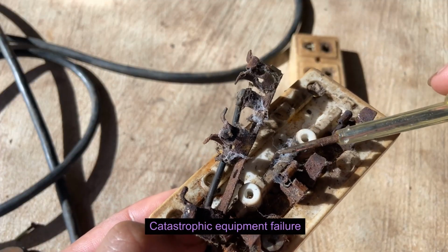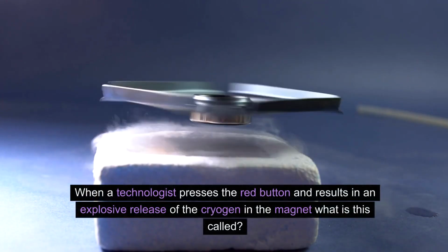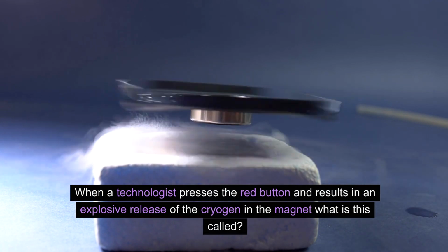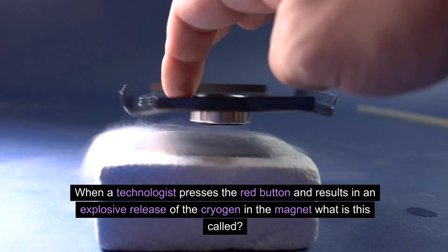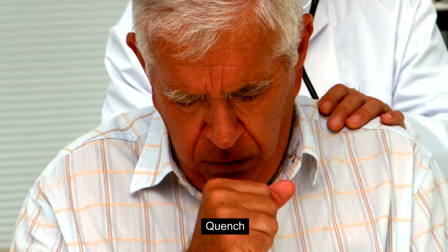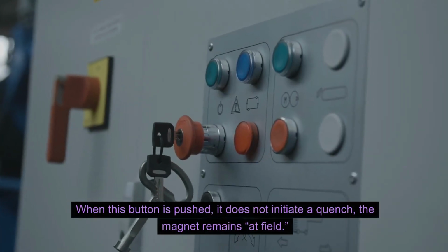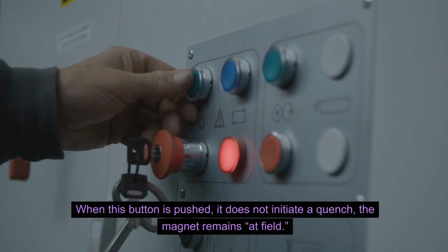Catastrophic equipment failure. Question: when a technologist presses the red button and it results in an explosive release of the cryogen in the magnet, what is this called? Answer: quench. When the emergency stop button is pushed, it does not initiate a quench. The magnet remains at field.